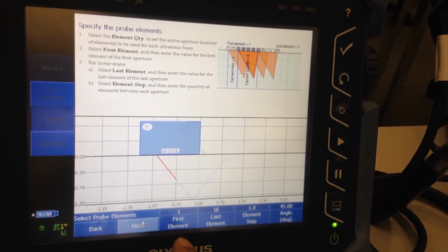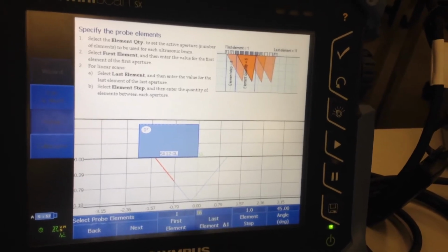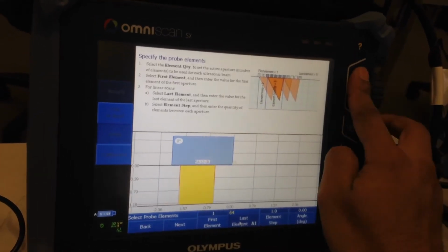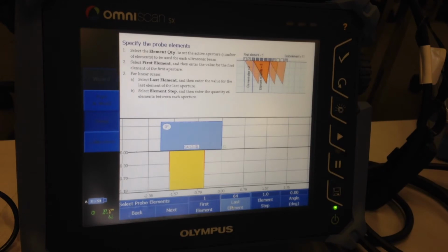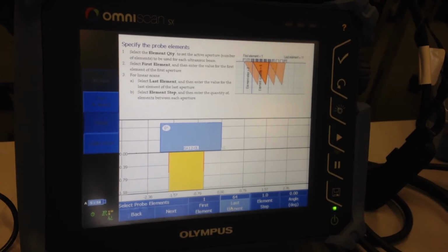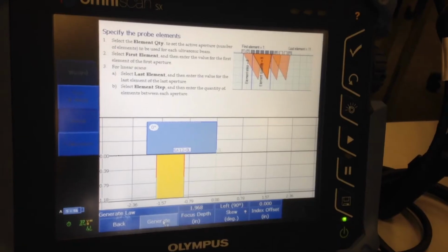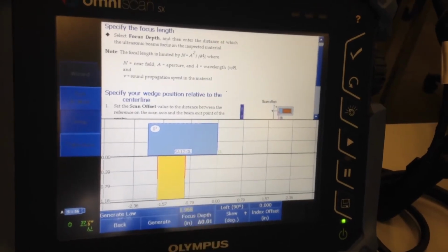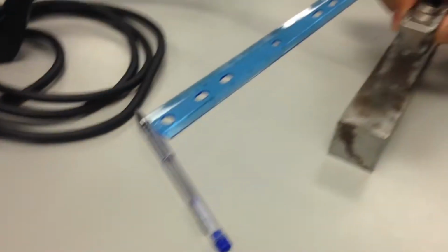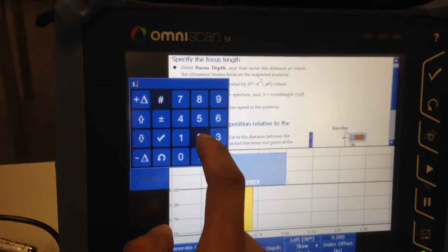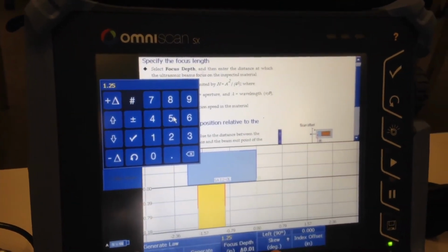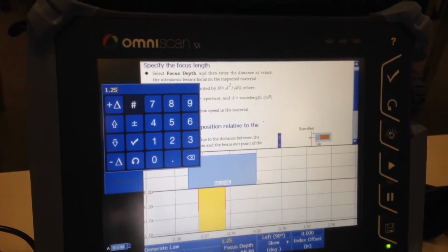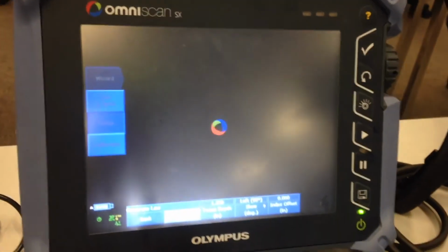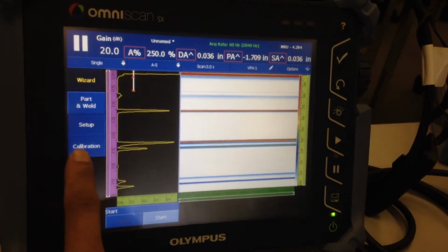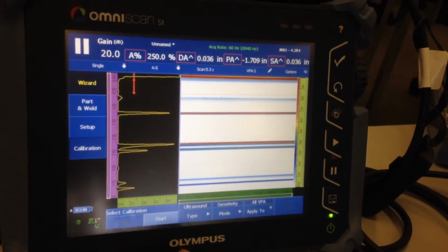First element 1, the last element used all the way up to 64. Also watch the angle, in this case is 0. Then click Next. Focus depth, I want to set my focus depth sound beam to focus at the thickness of my calibration block, so leave it on 1.25 and then click Generate. Next I move to calibration once I set my focal laws.